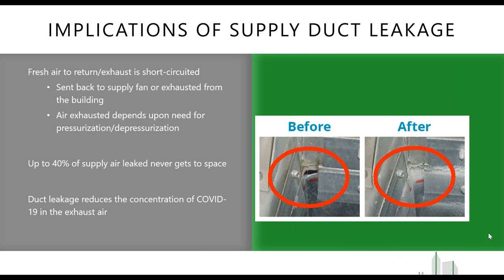So let's talk about the implications of supply duct leakage. The fresh air to the return or the exhaust is short-circuited. That means it's sent back to the supply fan or exhausted from the building, and the air exhausted depends on the need for pressurization or depressurization. Up to 40% of the supply air leaked never makes it to that space. So all of that air that you're trying to get to the space is never going to make it there because of duct leakage.